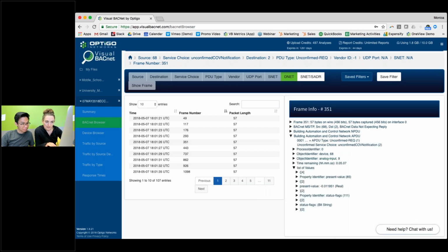Again, it comes back to what we always come back to: we don't know what that is on. If it's an iceberg that's going to melt, or some crazy thing, maybe you need that, in which case you should take it off that network and reduce the amount of traffic on that little MSTP network. Otherwise, you probably don't need it to be quite so sensitive, so reduce it. It really depends on what it's sensing. Based on your application, I would go back and check whether you need it that often.